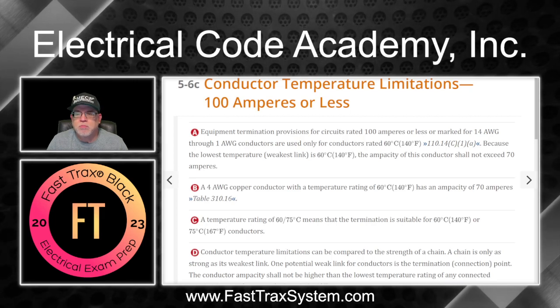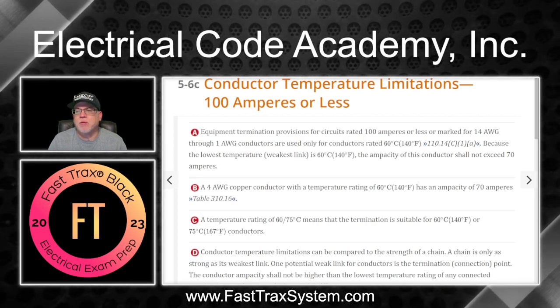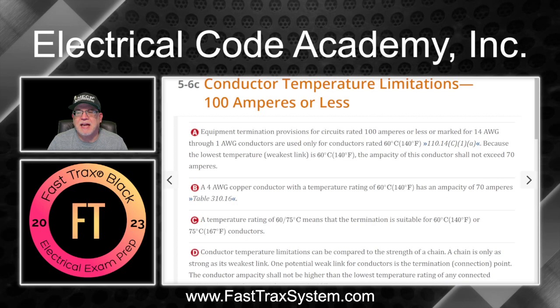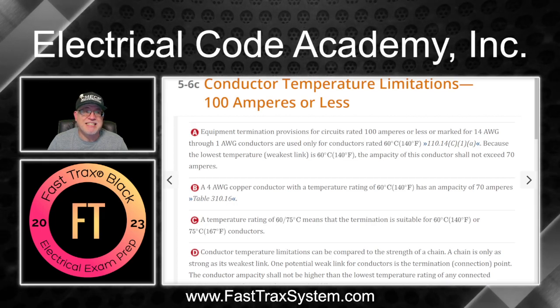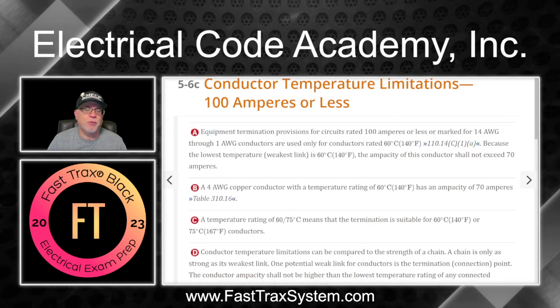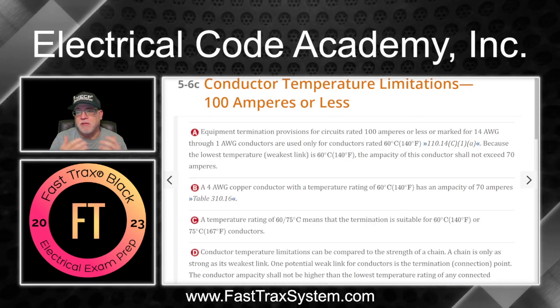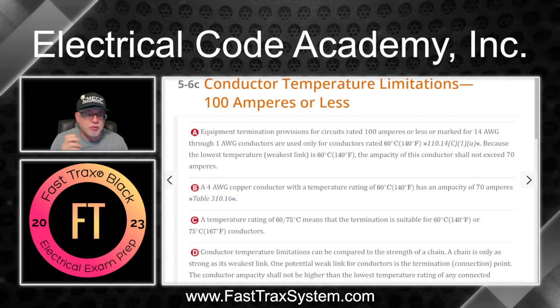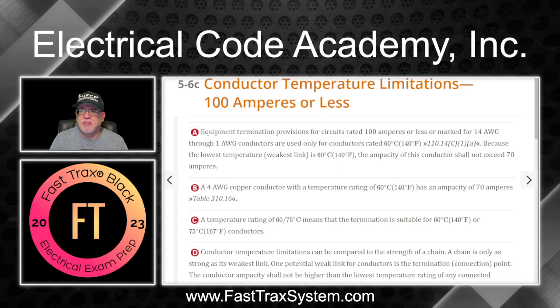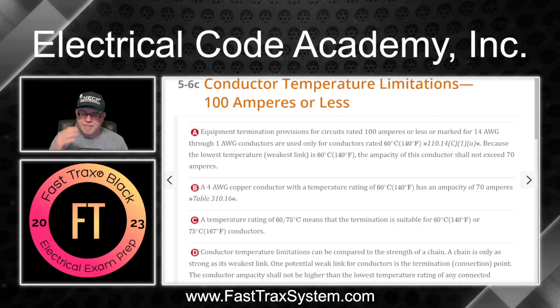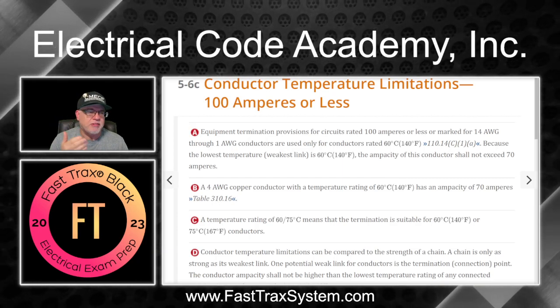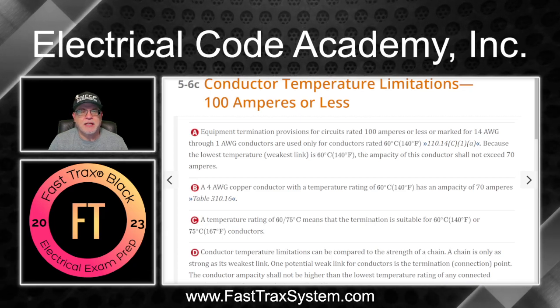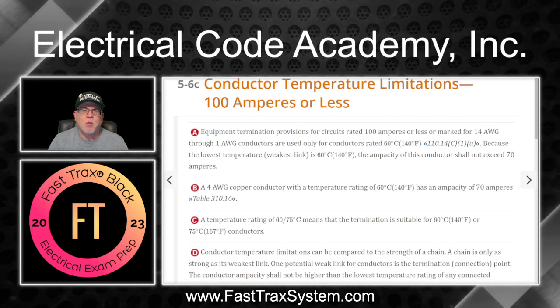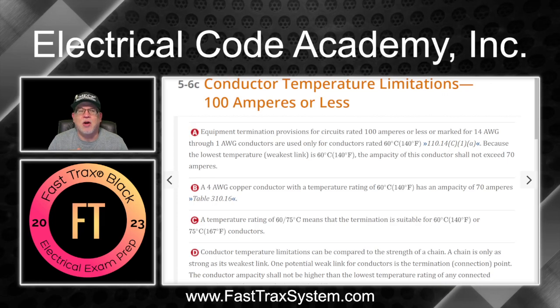Generally, this would be a conductor utilized under the 60 degrees C ampacity value. If we didn't know anything else, we would say, okay, if it's 100 amps or less, or conductor sizes of 14 through 1 gauge, then it's going to be 60 degrees C ampacities. That's just point blank. But what we're going to learn is that that is not always the case.